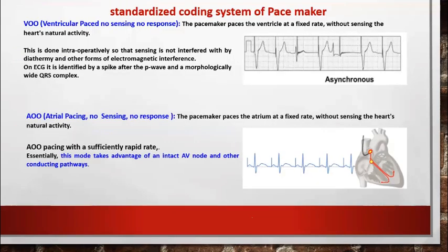So now I'm going to talk about the first letter, which identifies the pacing. You can see VOO: it means the pacemaker paces the ventricle at a fixed rate without sensing the heart's natural activity. Now this VOO is done intraoperatively to avoid electromagnetic interference. I will talk about it in the coming slides also. This is done intraoperatively so the sensing is not interfered with by the diathermy or other forms of electromagnetic interference. On ECG, it is identified by spikes after the P wave.